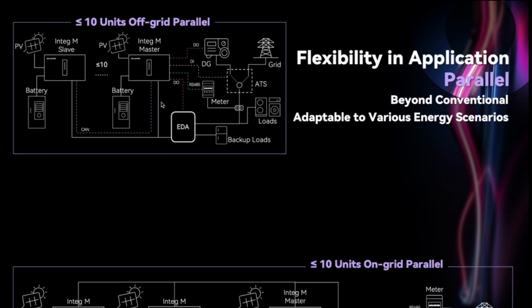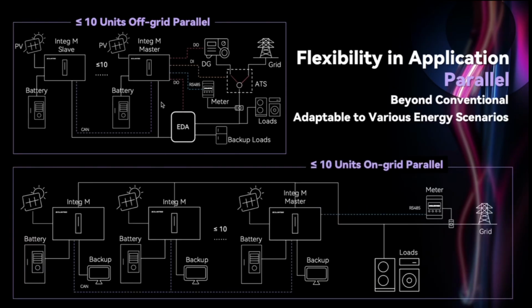And our system also supports up to 10 units for both on-grid and off-grid parallel, which makes it ideal for some large commercial projects or sites with high energy demands. For the off-grid parallel systems, we can also connect a diesel generator, either through the ATS or directly via the on-grid port, providing additional power security whenever the grid is unstable. And to ensure reliable and smooth switching between on-grid and off-grid operation, we will need an EDA backup box, which is essential for off-grid parallel setups.